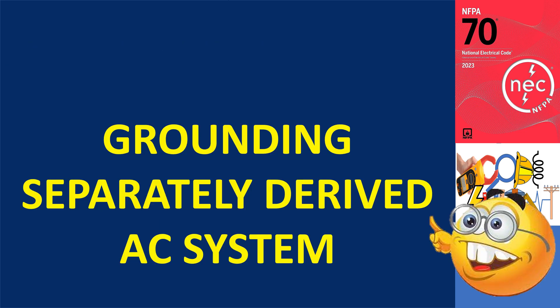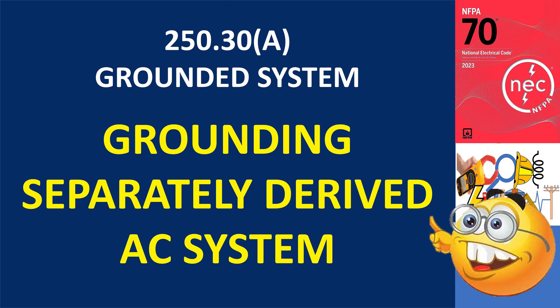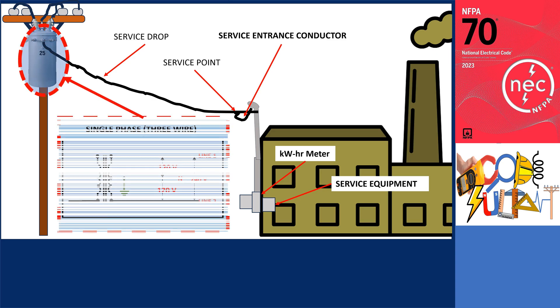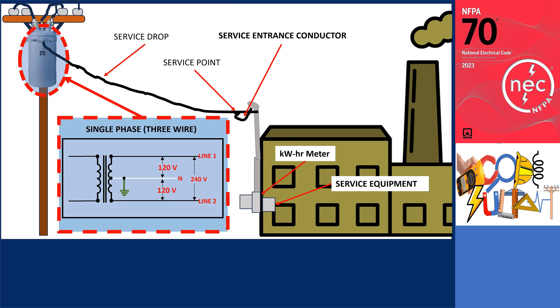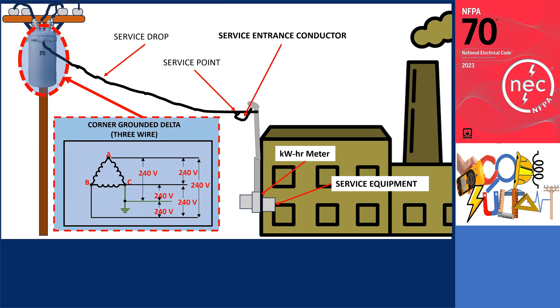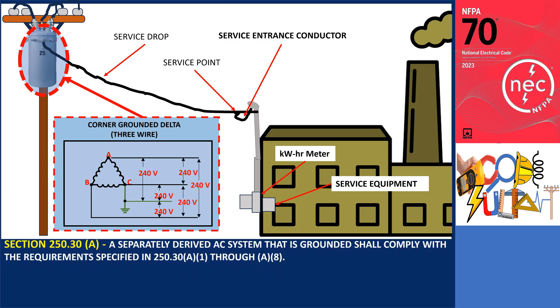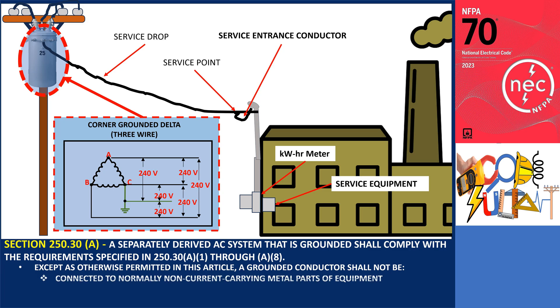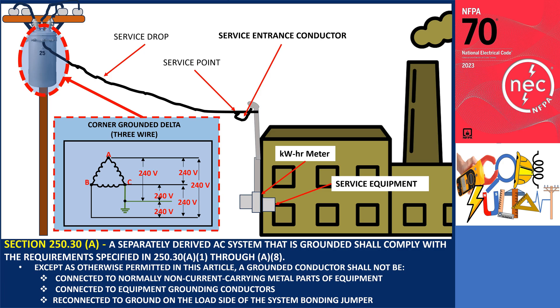Grounding a separately derived AC system connected to a service grounded system, as outlined in section 250.30: if the premises wiring is supplied by a service AC grounded system, such as a single-phase three-wire system, a three-phase Y four-wire system, a high-leg delta four-wire system, or a corner-grounded delta three-wire system, grounding for the separately derived system must comply with 250.30. Further, this section prohibits the grounded conductor from being connected to non-current carrying metal parts of equipment, being connected to the equipment grounding conductors, or being reconnected to the ground on the load side of the system bonding jumper.